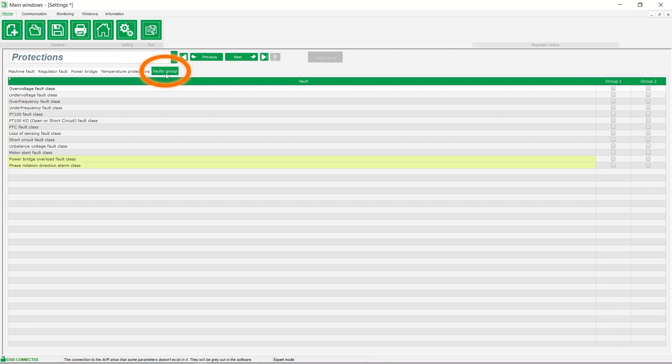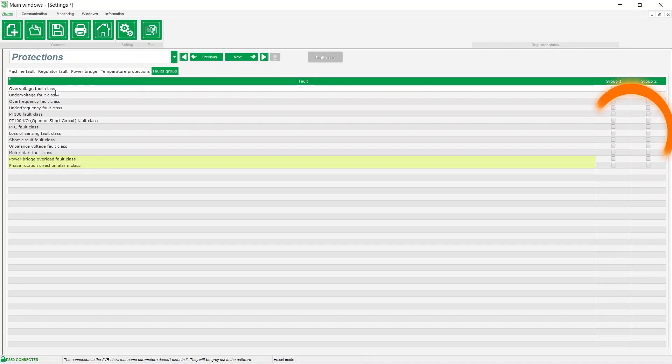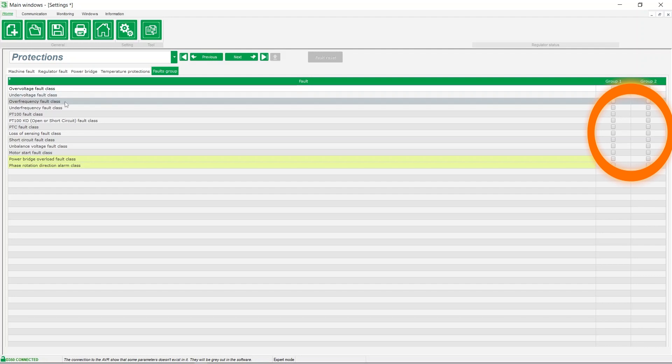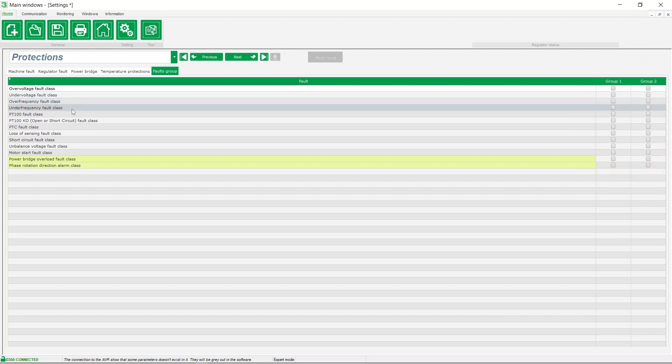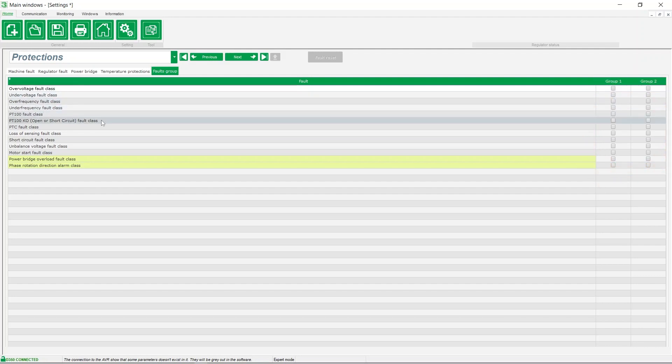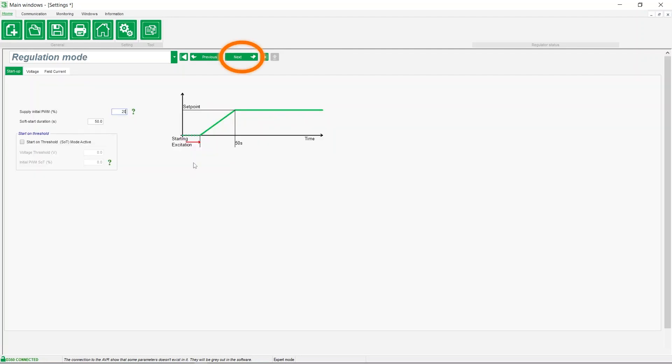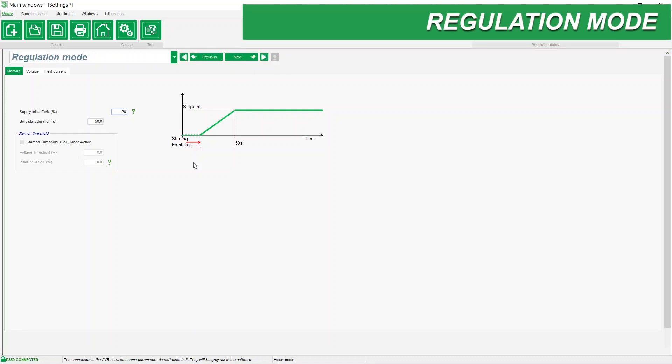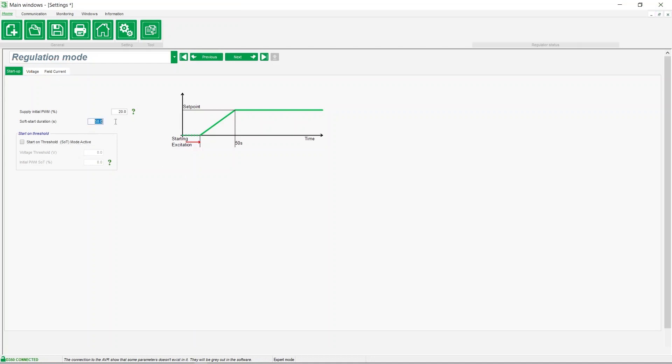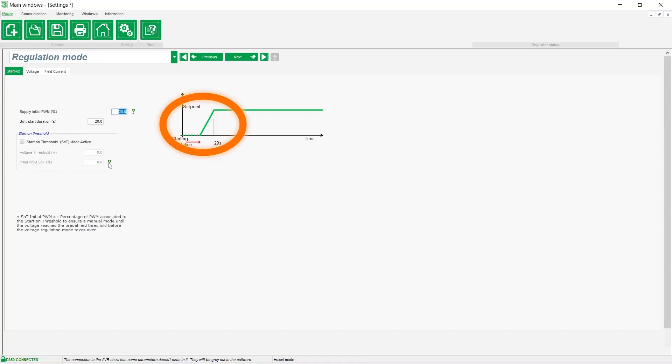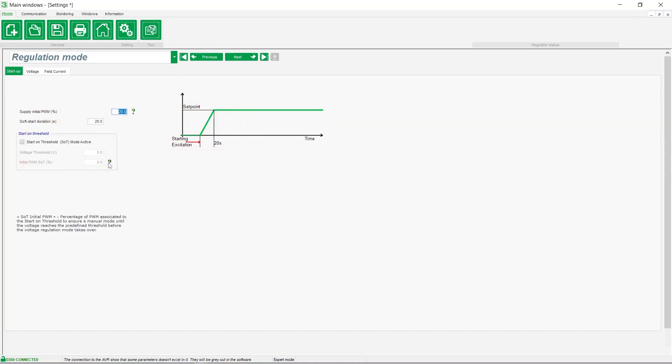To better manage event recordings, we can group them into fault groups. Each group can be assigned to a digital output, for example. Let's move on to the regulation mode. There are two regulation modes: voltage and field current. In the startup tab, the PWM value is predefined based on the alternator's excitation type. You can optimize the alternator's operation by modifying the voltage build-up slope and enabling start on threshold mode.